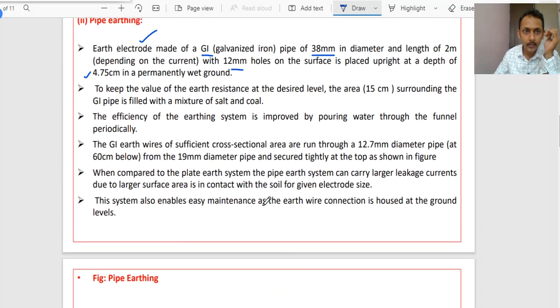So here, to keep the value of the earth resistance at the desired level, the area surrounding the GI pipe should be filled with a mixture of salt and charcoal, which is going to reduce the earth resistance. By making this arrangement, the earth resistance will be reduced. Now the efficiency of this entire earthing system can be improved by pouring water through the funnel periodically.